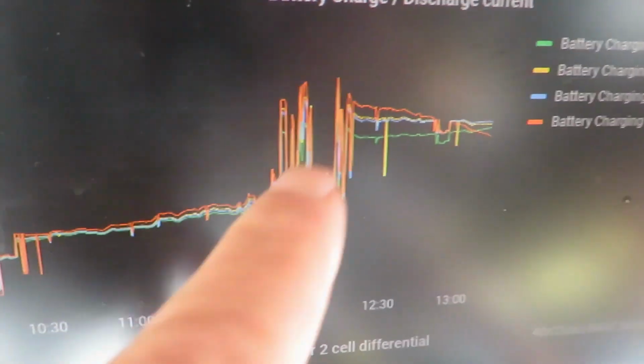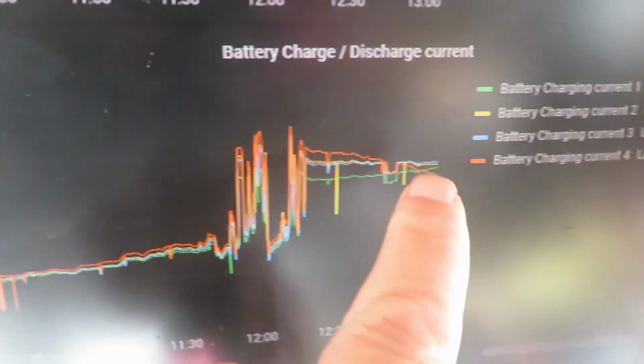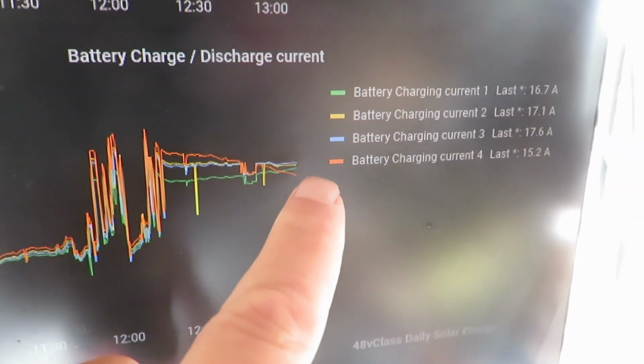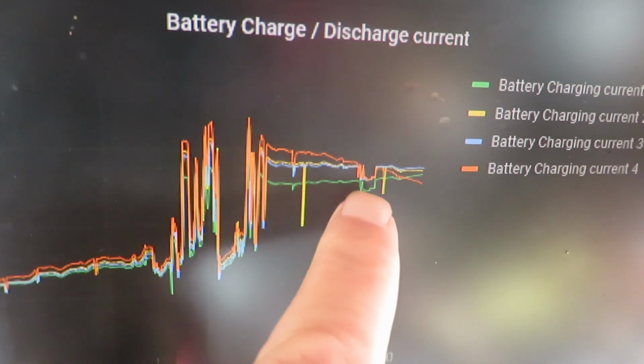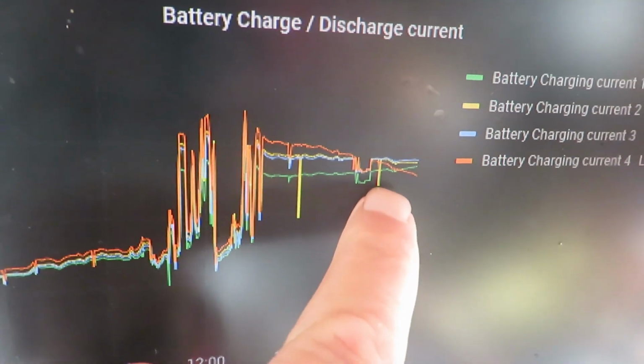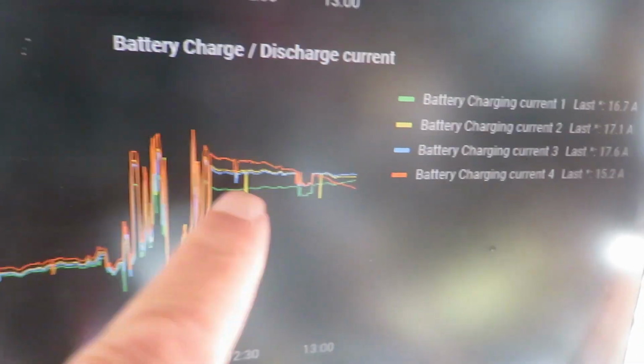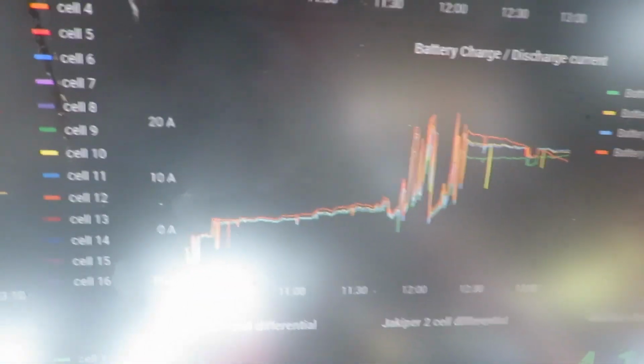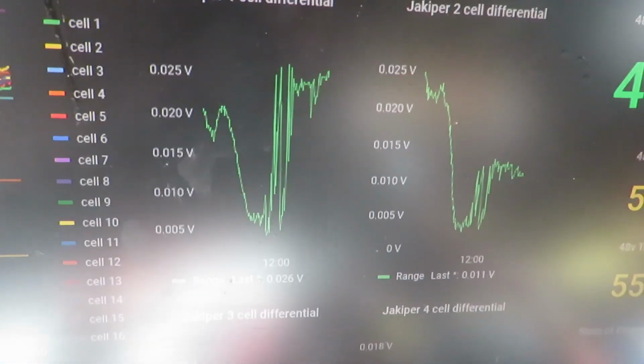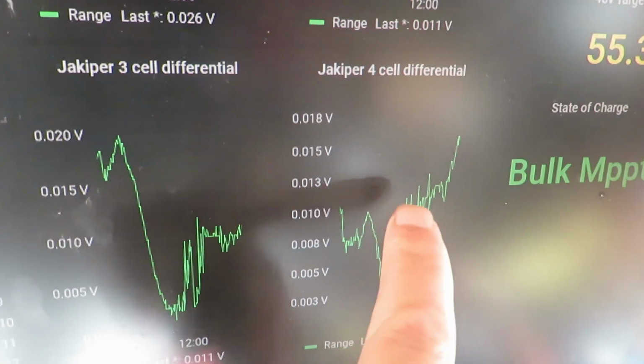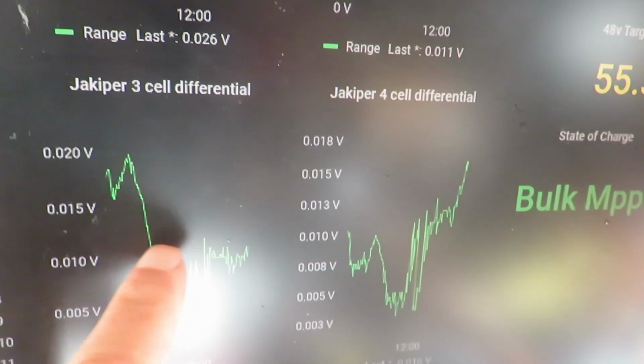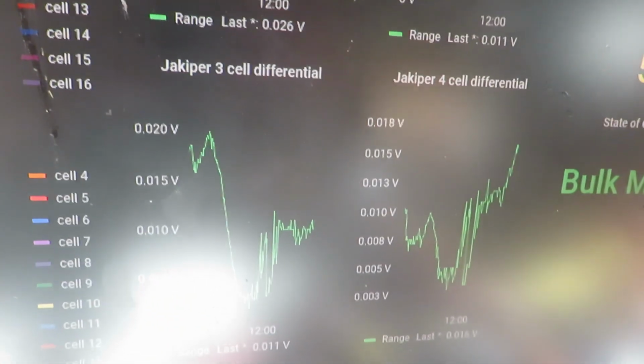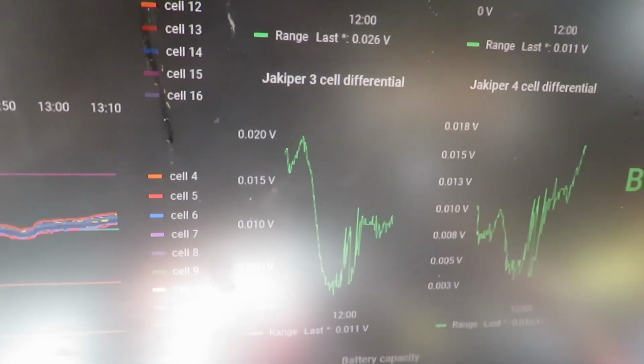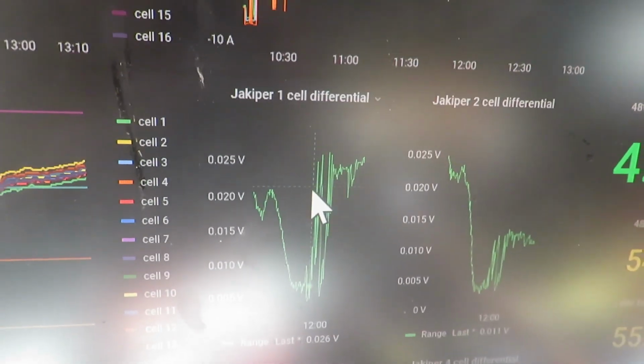Here's the current. It's dropping some on battery number 4. Let's see what the differential is. The differential is not too out of line, it's less than 18. None of them are too high, so they haven't gotten up to the full point yet, because it'll go higher.